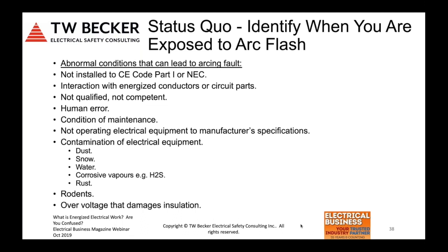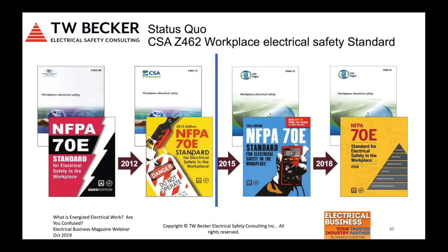Obviously, condition of maintenance is another abnormal condition that could increase the probability or the likely occurrence of an arcing fault, an arc flash, or even a shock risk exposure. Not operating the equipment to manufacturer specification, contamination of the electrical equipment, rodent intrusion, over voltage, and damages to insulation. So this is a list of abnormal conditions where we have a change in state and the likelihood of occurrence can increase.